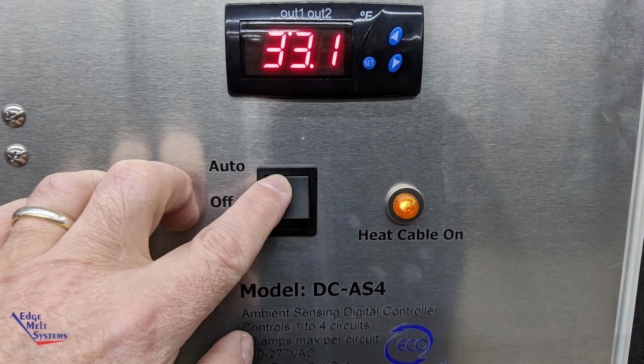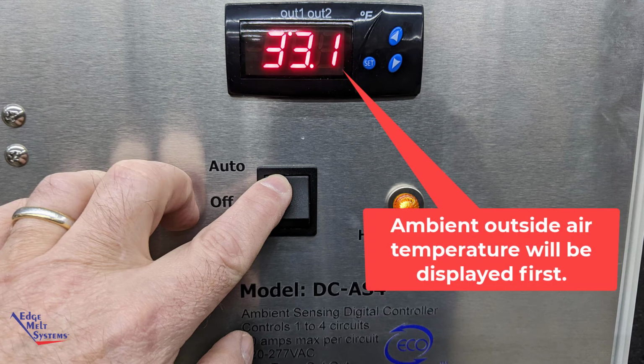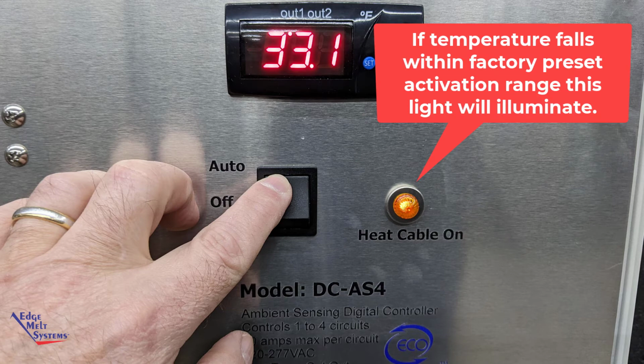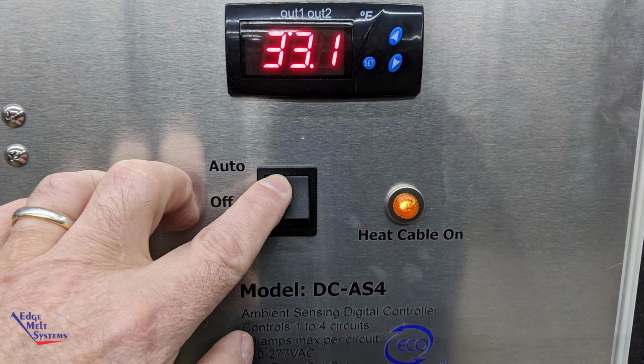To test the automatic function of the controller, depress the 3-position switch in the up or auto position, and the temperature display will illuminate, showing outside ambient temperature. Check and make sure this is within range. If it is between 5 and 35 degrees, the heat cable on light will illuminate. If it's outside of that range, the heat cable on light will not illuminate. If you get an error message on the display, it means the temp probe is not connected properly.